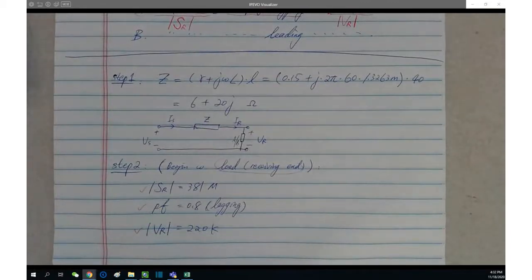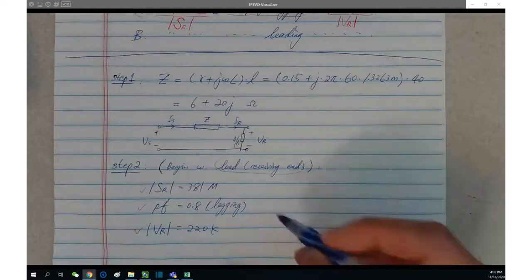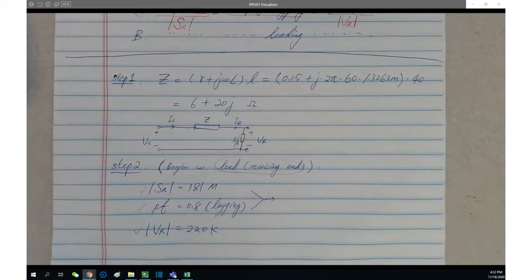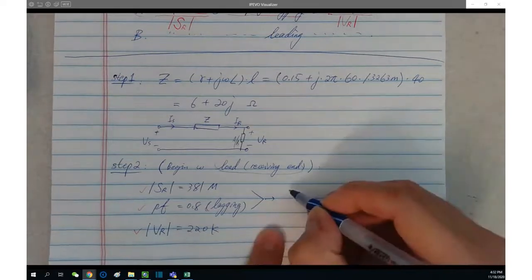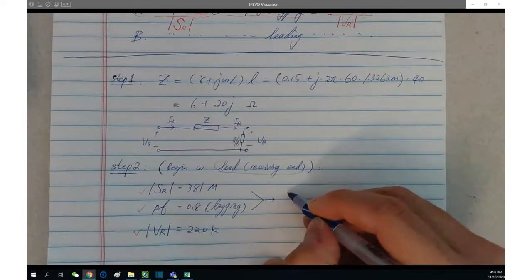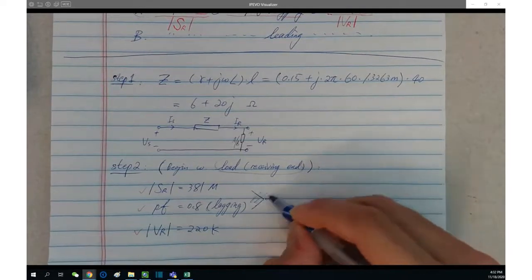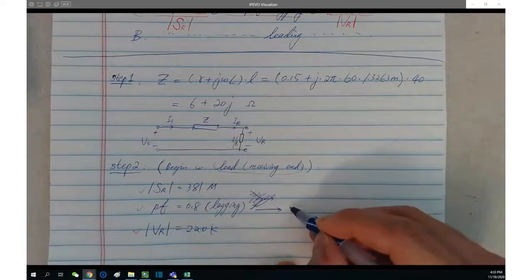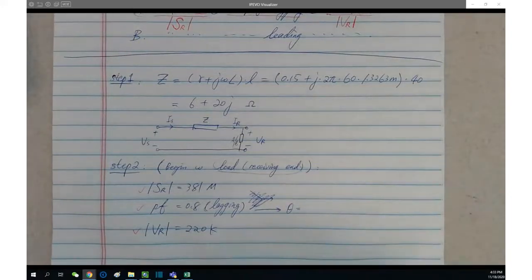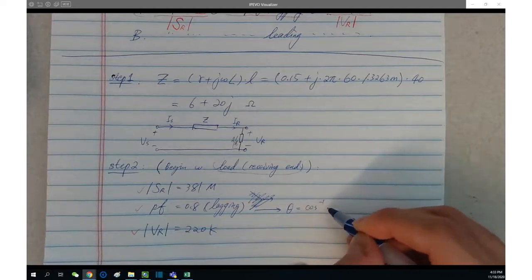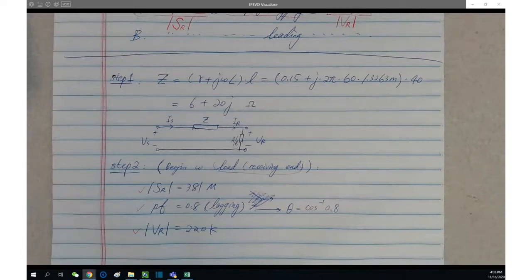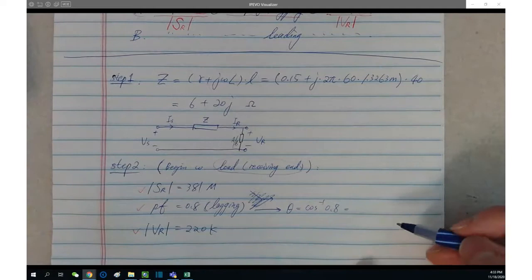All right, if no comments, then we can move on. Let's see how to deal with this translated information. First of all, we need to recall the knowledge back from module two, I think, when we talked about single-phase and three-phase power systems, the power and power factor, et cetera. Here, we need to deal with this based upon the power factor. The power factor information itself is providing you what? Angle, right? Impedance angle equals the inverse cosine of the power factor value.